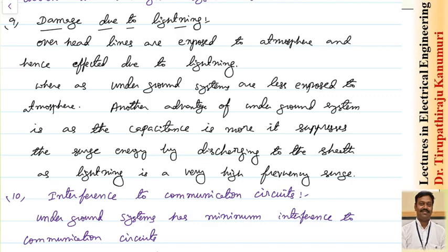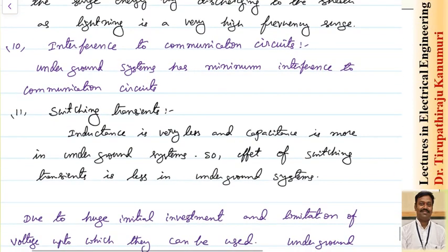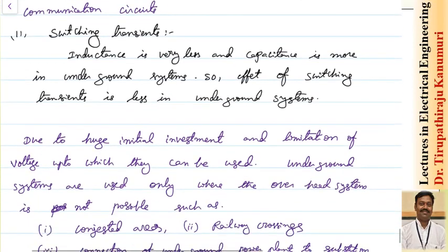Charging current: as conductors are very near to each other in underground systems, capacitance and hence charging current are more compared to overhead systems. Damage due to lightning: overhead lines are more affected due to lightning, whereas underground systems are less exposed. Underground systems have more capacitance, which suppresses surge energy by discharging to the sheath, so the effect of lightning is very less on underground cables.